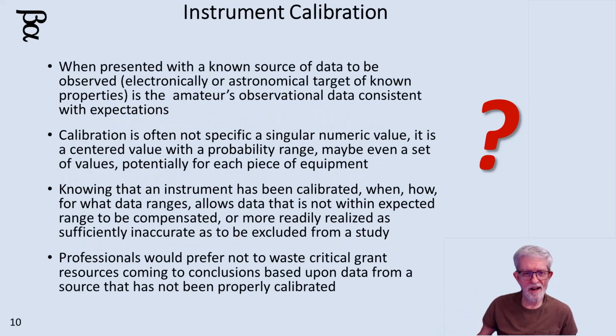Now that it's been certified, what about calibration? Sometimes equipment has components that are adjustable, and therefore they can throw off the observations. You need to know what the calibration data is. When was the last time it was calibrated? Does it need to be calibrated or not? Is it self-calibrating? Which is not often, but sometimes. What was the process by which it was calibrated? Who signed off on the calibration?